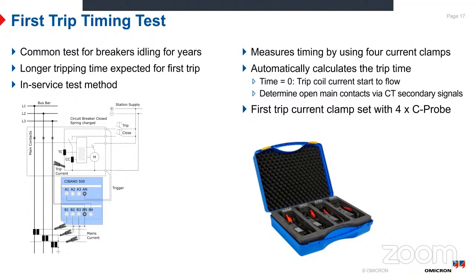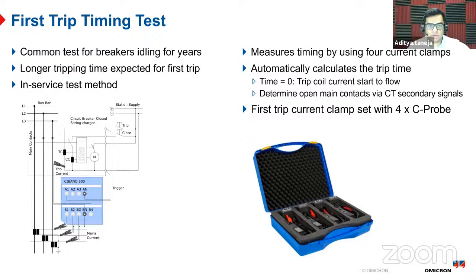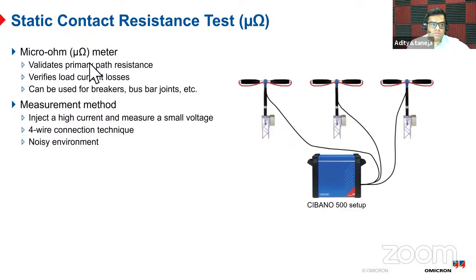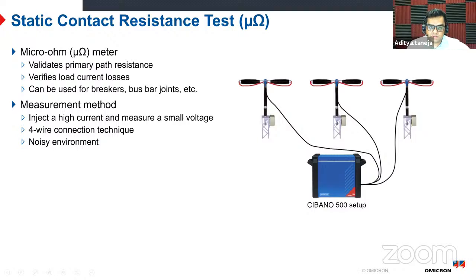So the main thing in non-invasive testing is that timing measurement has to be done. The other thing is contact resistance measurement, which tells us the resistance offered by the contacts when the breaker is closed, so main contact resistance. We do that by injecting high current, typically 100 ampere, and measuring the voltage drop across those contacts. From current and voltage, we can measure resistance. So that is again very easy.